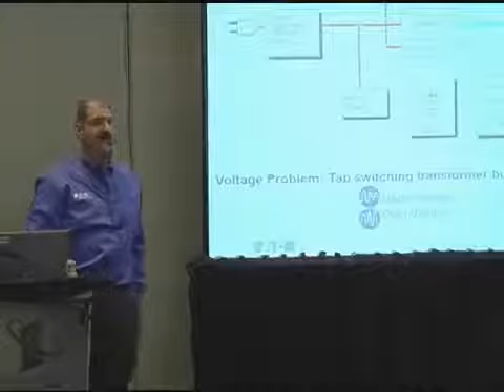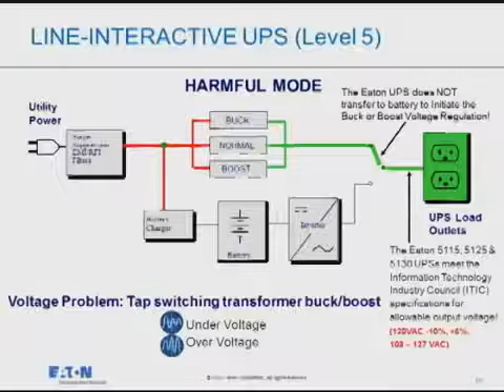So if I have a 10% overvoltage, I'll buck it down to nominal voltage. If I have a 10% undervoltage, it'll boost it up to nominal voltage. What I'm doing through the buck and boost is saving cycles on the battery. If I can save cycles, I increase the lifespan of the battery, and therefore the operation of the UPS. So now I'm increasing my lifespan to typically about 3 to 4 years, anywhere from a 25 to 50% increase in battery time.